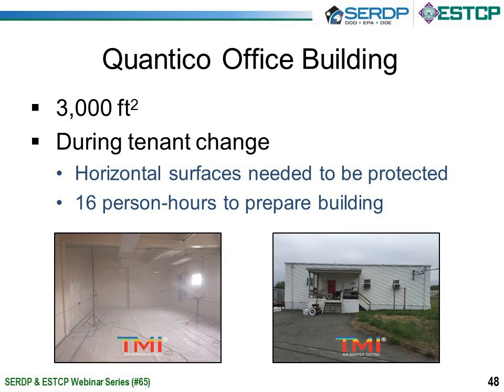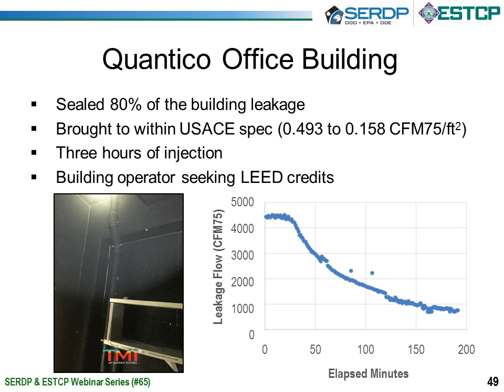To prep this building, it took about 16 person-hours of preparation, which is about a 2-person team, about 1 day of work. And then we started sealing, and we were able to seal about 80% of the overall leakage. It went from 4,500 CFM at 75 pascals down to below 1,000. And this, again, brought this building to within the USACE spec, from 0.493 down to 0.158 CFM 75 per square foot. And this took place in only 3 hours of injection. So there was some significant preparation required, but the sealing time is actually quite short. And the building operator was really pleased with the overall result, and they want to seek LEED credits for this effort. So we were happy about that.